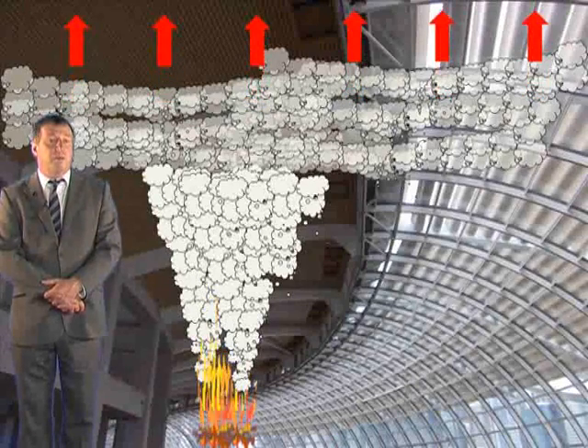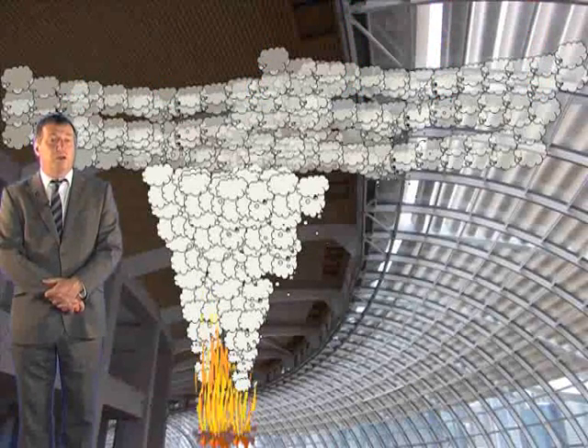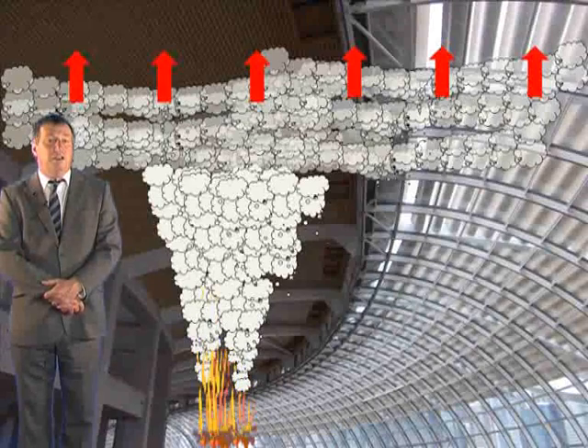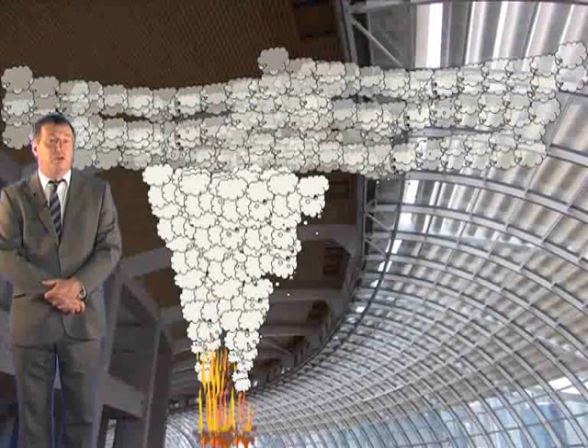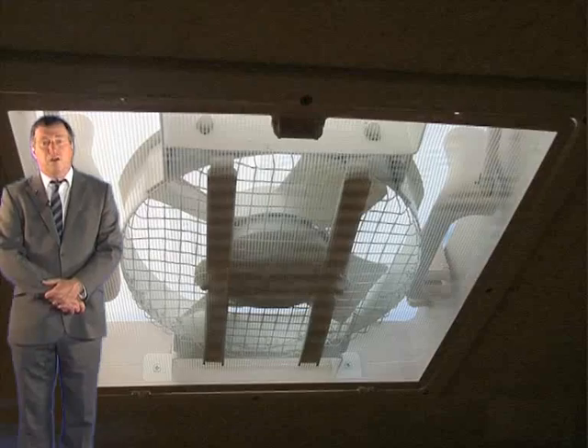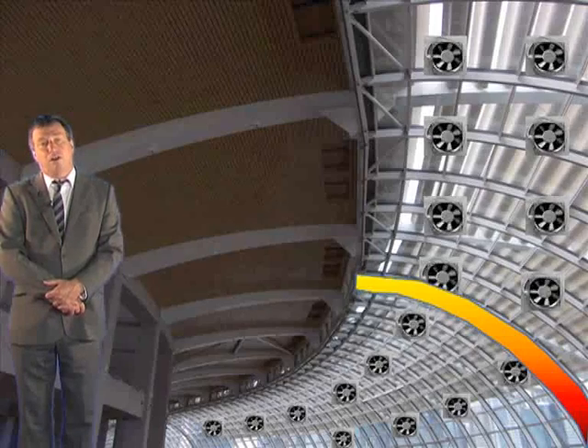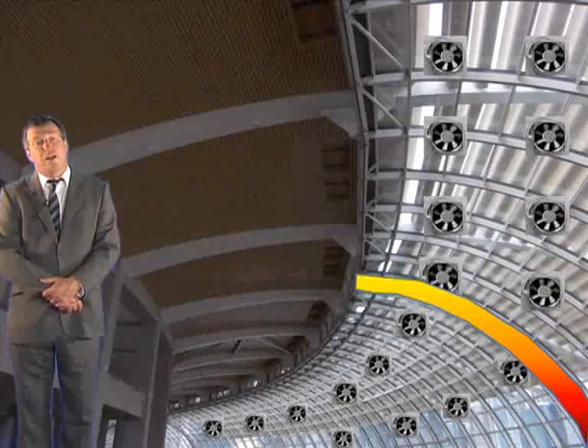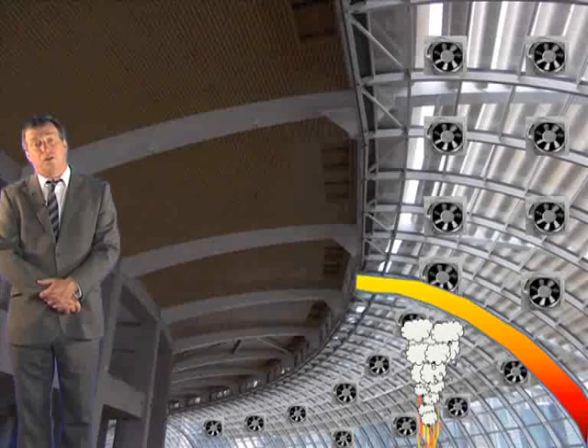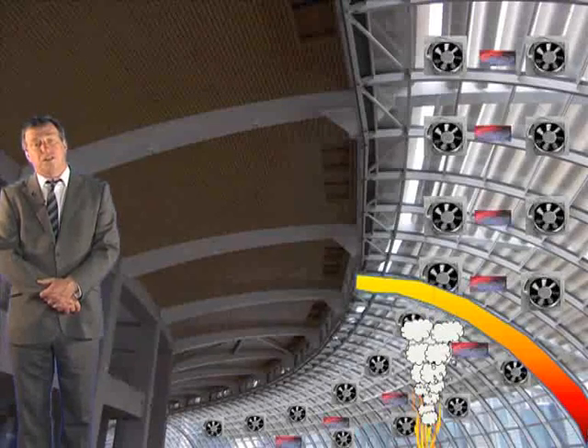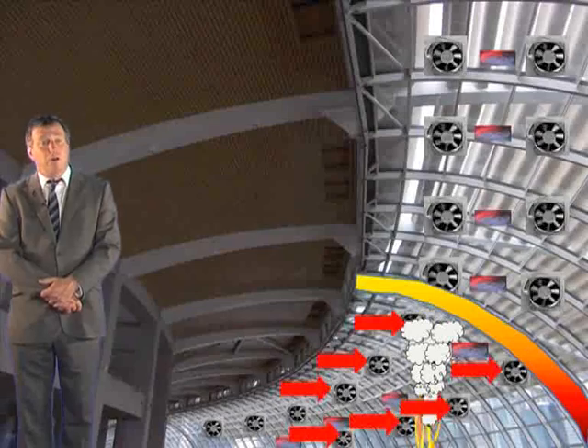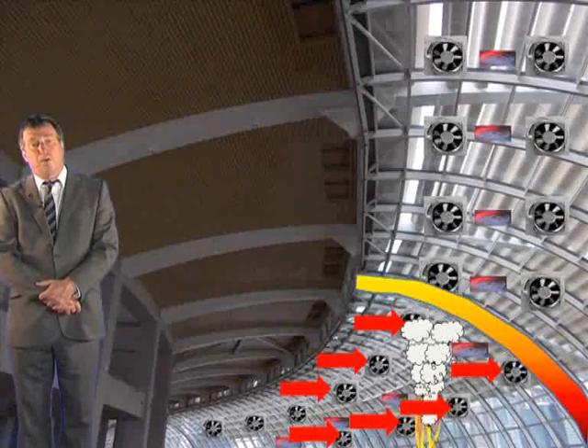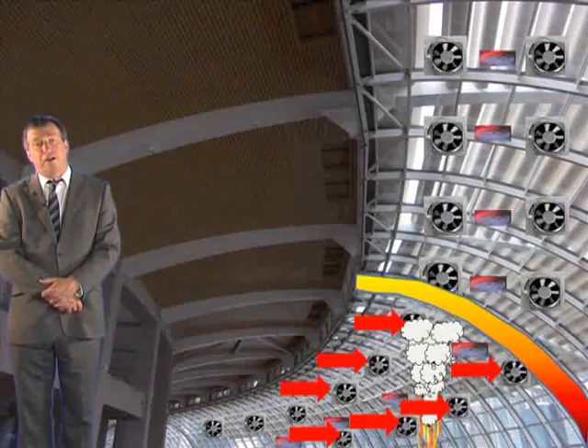It's designed so that the amount of smoke leaving the ventilators when the smoke is at its design height is equal to the smoke entering the layer from the plume. Mechanical ventilation is where there are electrically driven fans located at high level in the reservoirs, and these come into operation on detection of smoke within the reservoir. Only the fans in the fire-affected reservoir operate. Fans in reservoirs unaffected by the fire remain dormant.